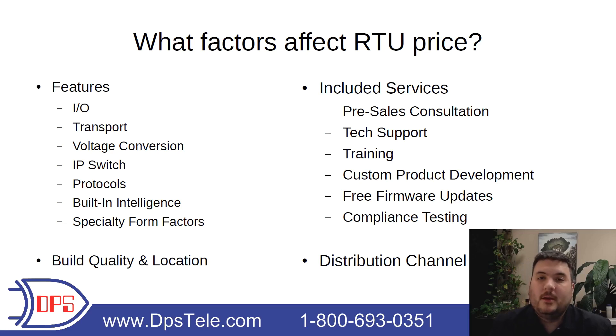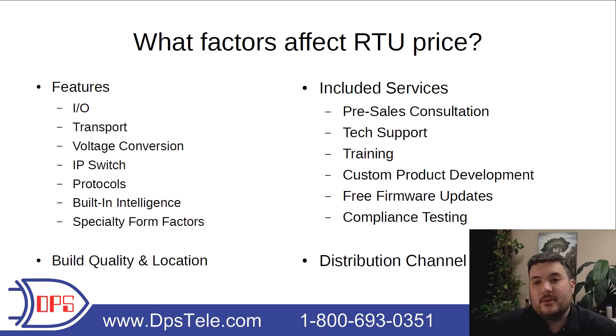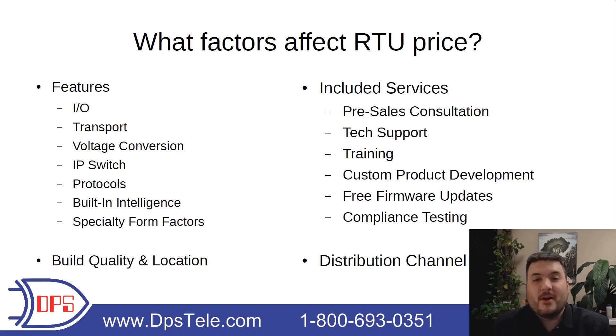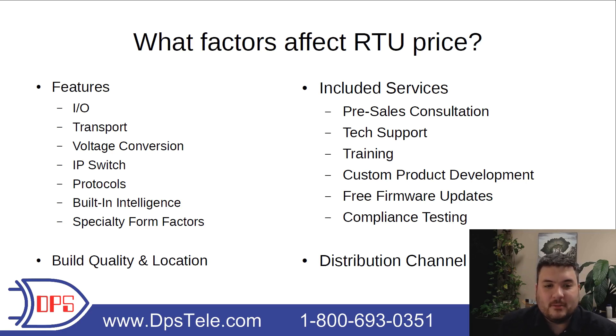Then we come to protocols. Is this an RTU that supports a nice industry standard, or is it something the manufacturer uses to trap you? They might have their own proprietary protocol and be trying to sell the RTU at a lower price because they know you'll then have to buy their overpriced, underpowered master station to go along with it. To free up your purchasing options for the future, look for SNMP, DNP, or Modbus — an open standard protocol like that.